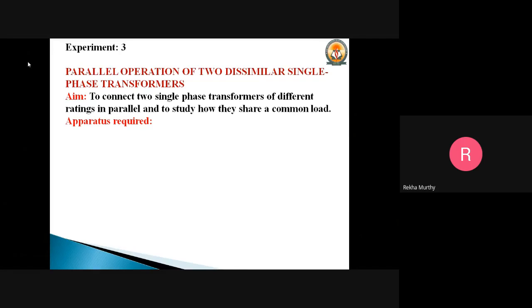Before we go with this experiment, we should know that transformers are said to be connected in parallel when their windings are connected to HV or LV bus bars, which are common to both. To meet additional demand on the power system, it becomes necessary either to replace the existing unit by a unit of greater capacity, or to install an additional unit to carry a portion of the additional load. Sometimes two or more units connected in parallel are preferred over a single unit.